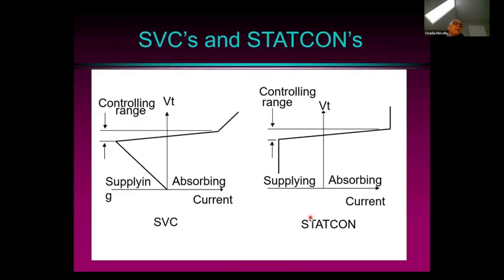We see the difference here between a static VAR compensator and a static condenser, where a static VAR compensator just switches capacitance into service as the voltage goes down. So if the voltage level is okay, you may be able to absorb some reactive power if you have shunt reactors. And then as the voltage goes down, you switch your shunt reactors off, switch your shunt capacitors in to try and boost the voltage.